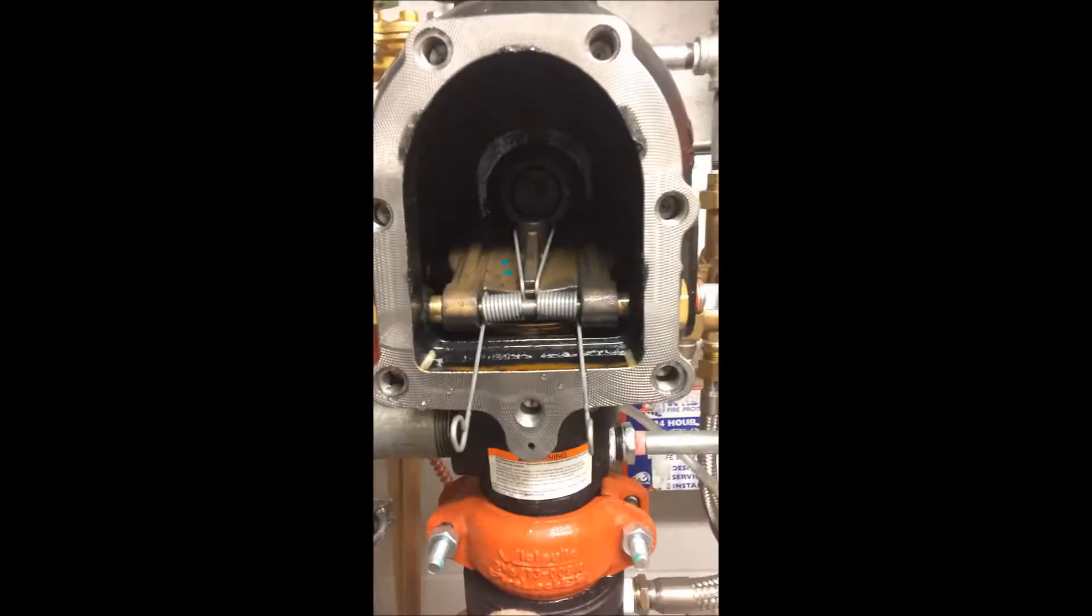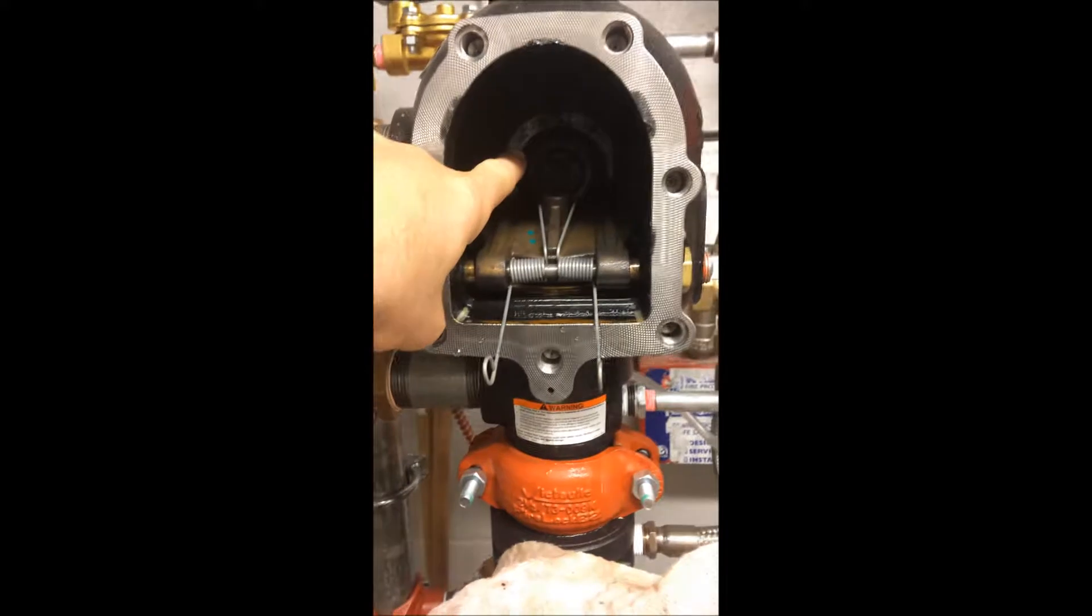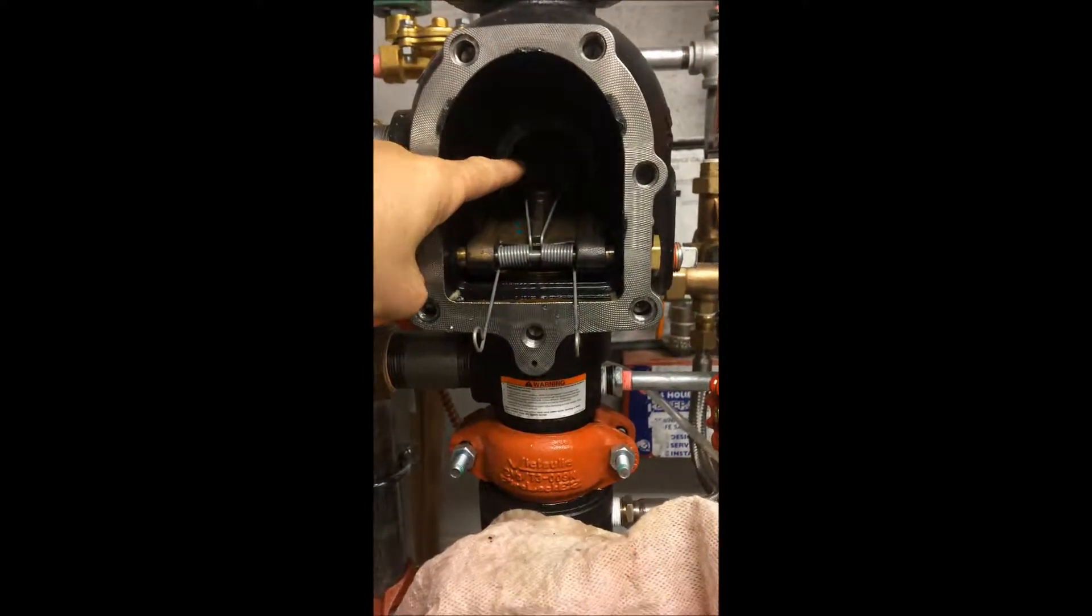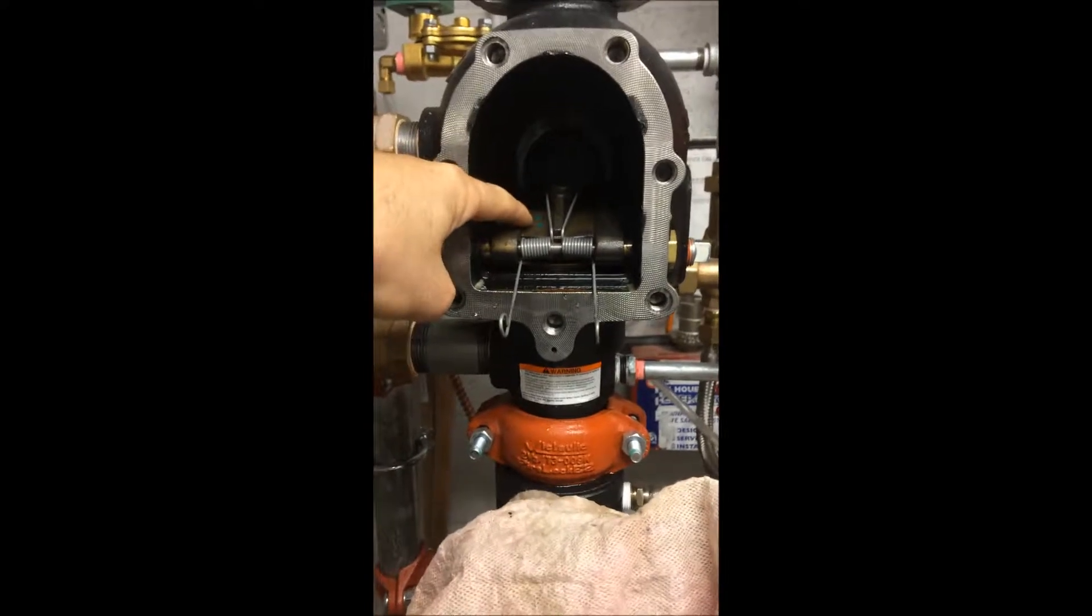It's a deluge valve. And we can go and reset it. And at the back here, it's a diaphragm that fills with water. And it's kind of like on a piston. It comes down and locks the seat into place.